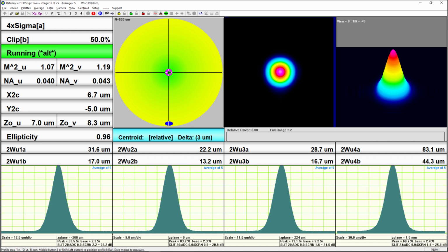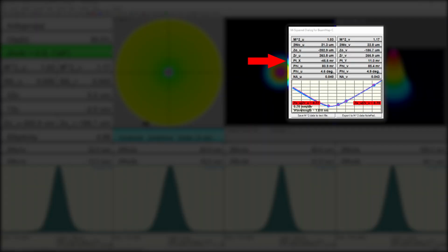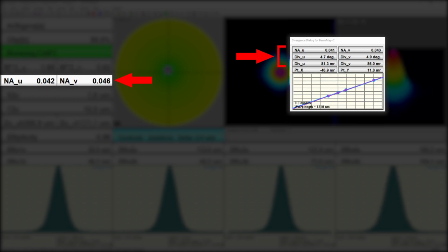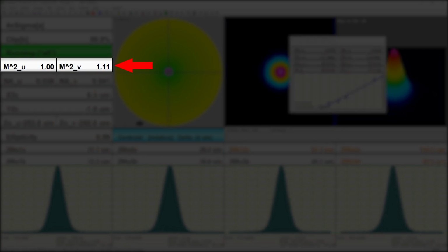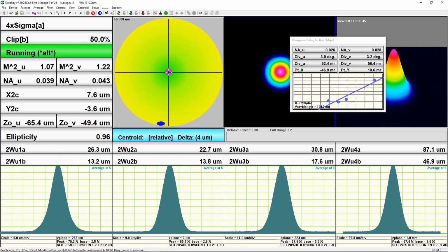With misaligned or unfocused beams, the BeamMap2 can deliver axial misalignment or pointing data, indicate the current focus direction, estimate the beam waist diameter at focus, estimate the off-axis distance of the focus, estimate m² and beam divergence, all in real time. The multi-plane scanning slits and robust software package enable real-time focus finding. Once you've found the focus, you now have access to the measurements for focus position in Z, the X and Y centroids, divergence, beam waist diameter, and m² with a sub-micron repeatability at 5 Hz.